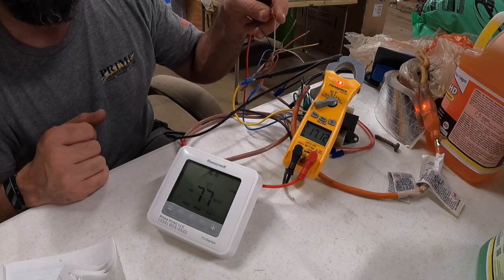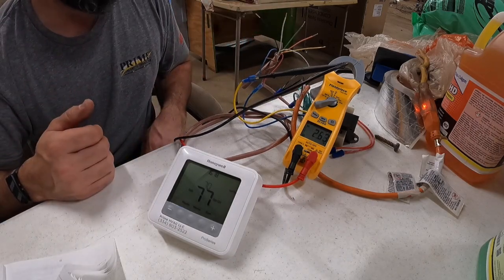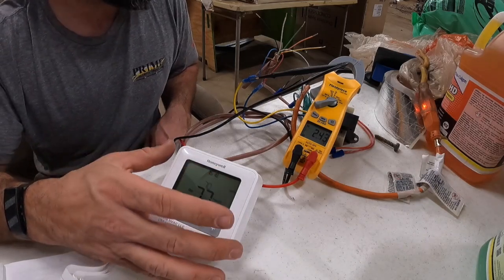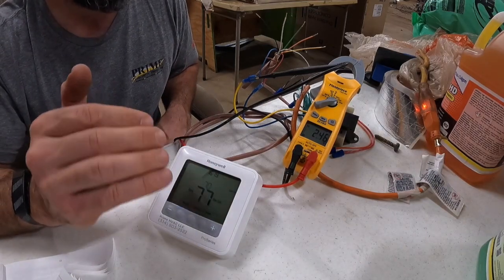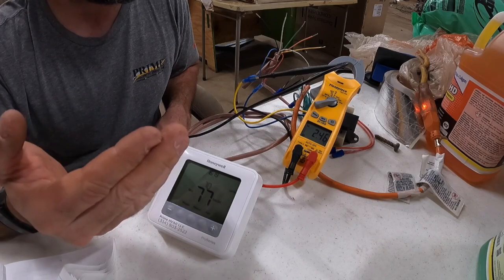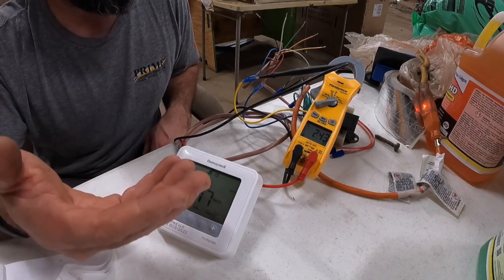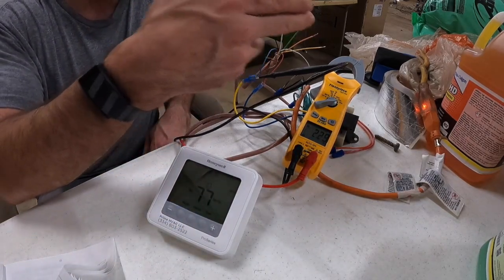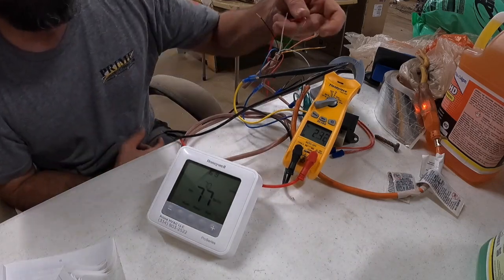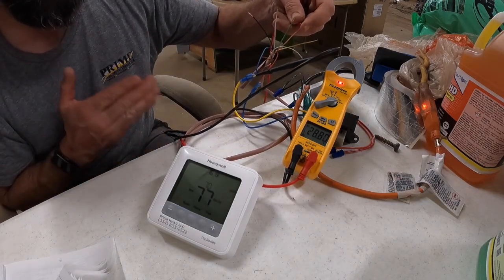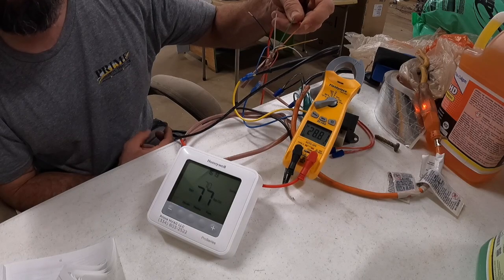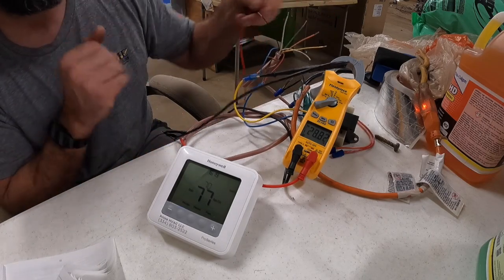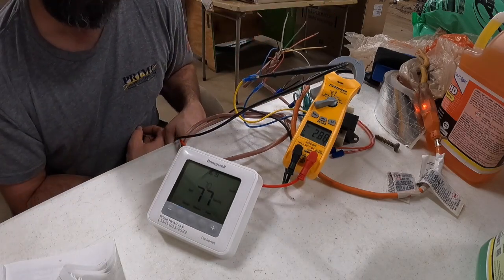Okay, now if this were a Rheem or a Ruud system, we would have had the thermostat set up to energize the reversing valve in heat, which is what B means. Same wire, which is the orange wire, but when we're calling for cool, it would not energize the O wire, because on Rheem and Ruud, it needs to be energized in heat mode.